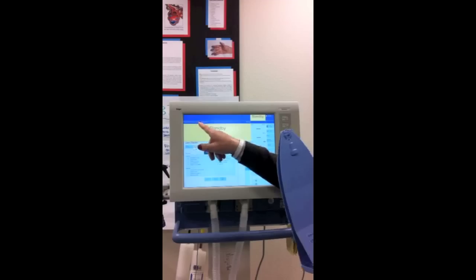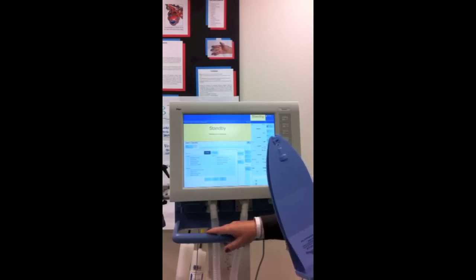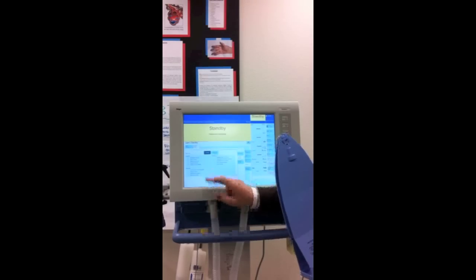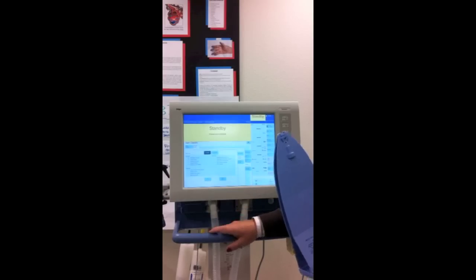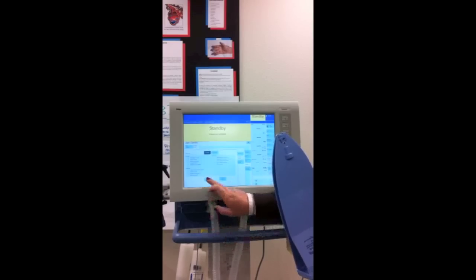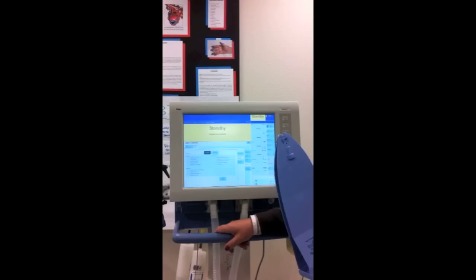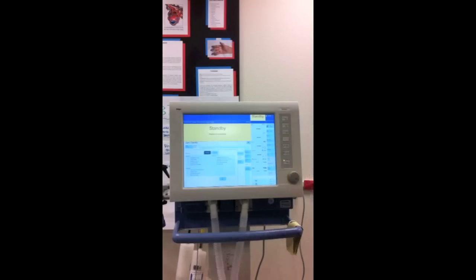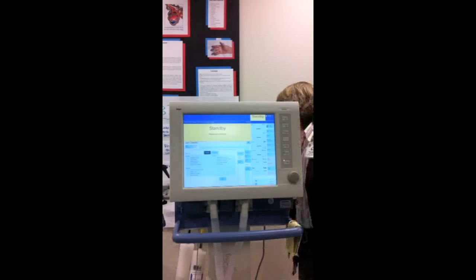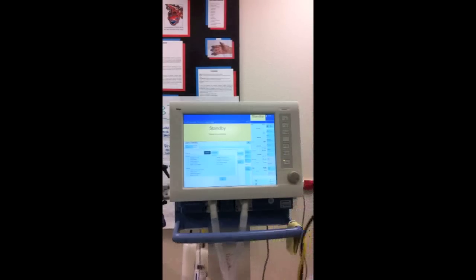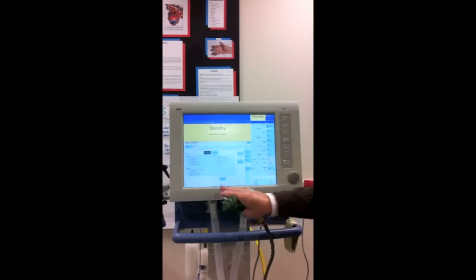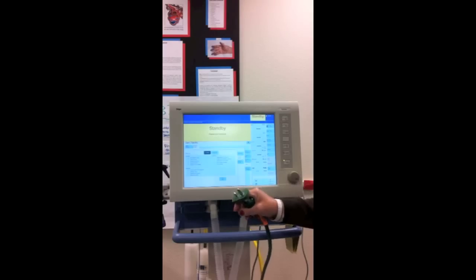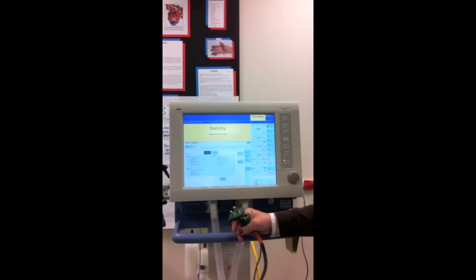Are the patient hoses correctly connected? Yes. So now we're going to say yes. Connect test lung to Y piece, confirm with yes. Connect air supply, disconnect oxygen supply. So now we'll disconnect our O2. And then it's going to start its check. Just do exactly what it tells you to do. Check is active, please wait.